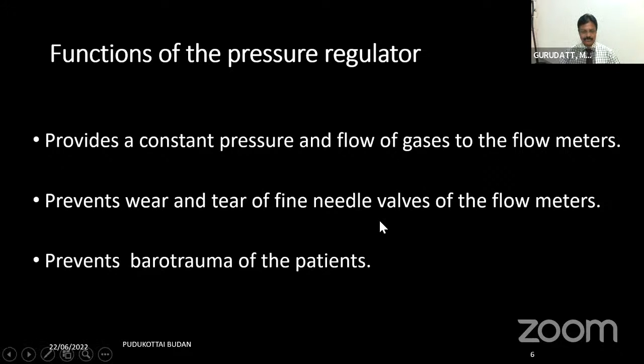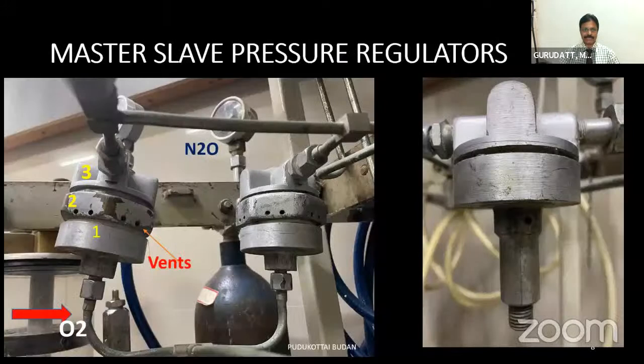So the majority of the time, what we have found is that when we ask the student what the function of a pressure regulator is, they directly say, preventing barotrauma of the patient. It is the least function of the pressure regulator. The main function is to maintain a constant flow of gases to the flow meters. So this is very important.